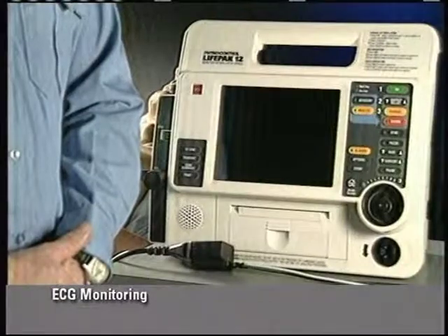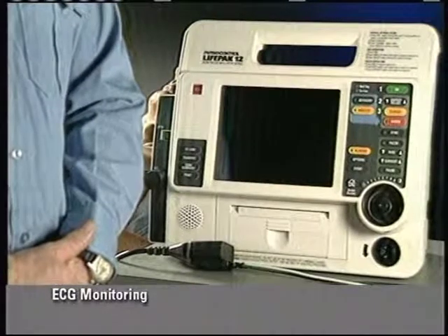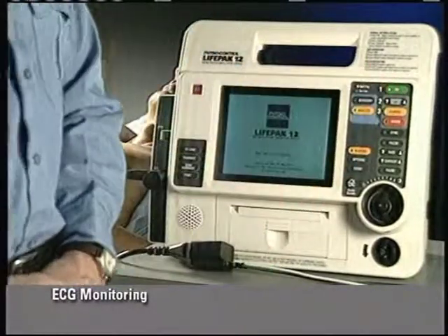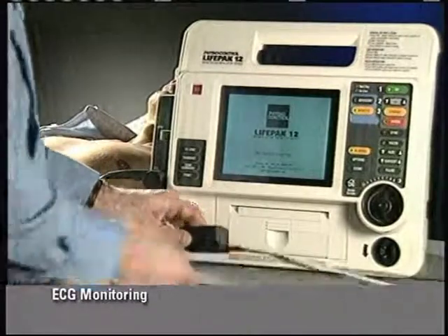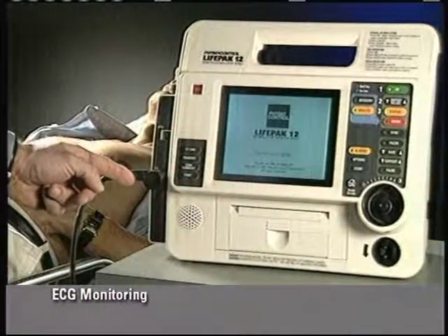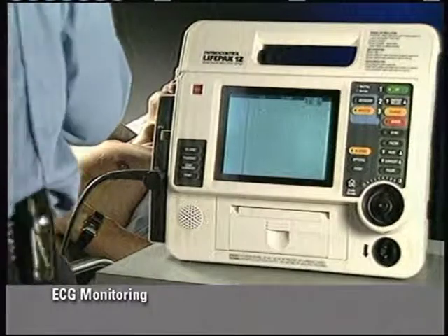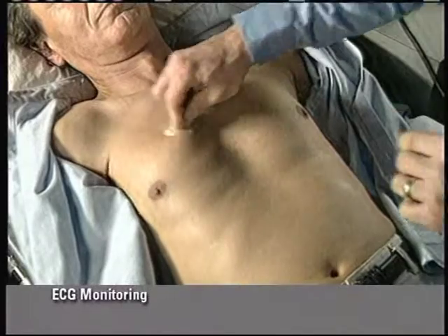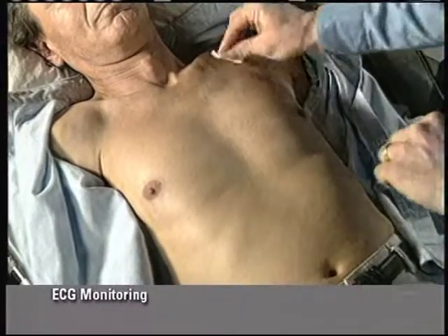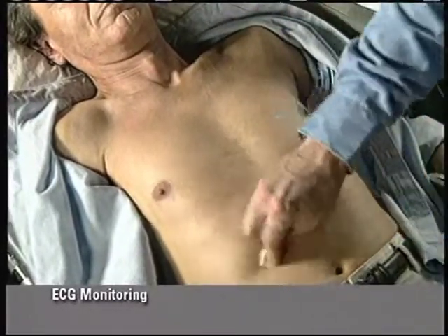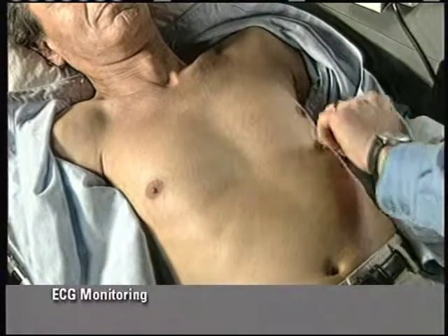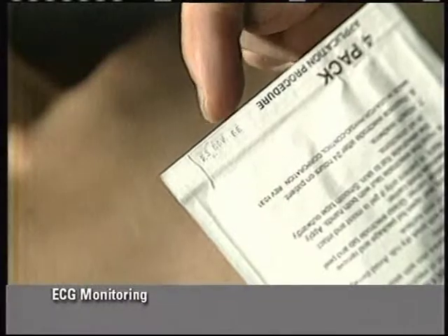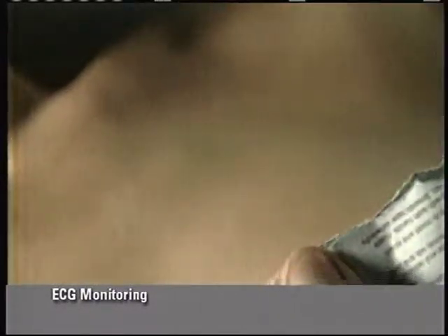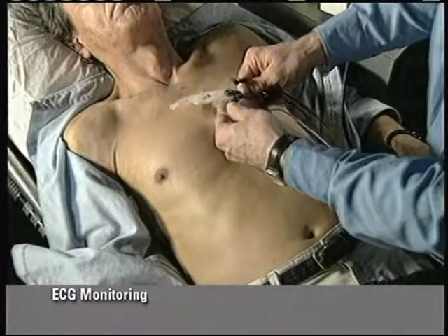To monitor the patient's ECG, press on. Adjust screen contrast if necessary. Connect the ECG cable to the monitor if not already connected. For the best signal quality, prep the ECG electrode sites by cleaning the skin with an alcohol pad, followed by a brisk rub. Shave the electrode sites if necessary. Confirm that the electrode's expiration date is not passed, and attach an electrode to each of the lead wires.